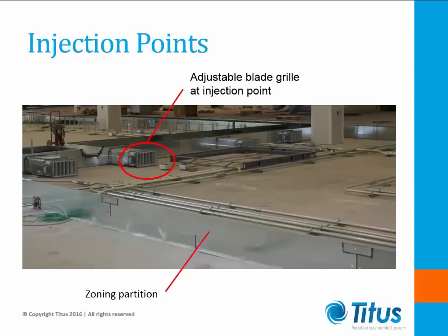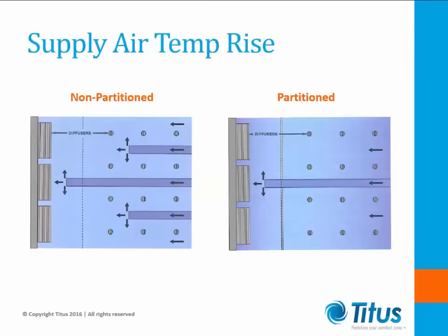In this slide, you can see both an injection point and some zone partitions. Notice that the discharge of the injection point has been fitted with a grill. You can also see how the zone partitions have been notched and sealed to go over conduit, plumbing, and other obstructions found beneath the floor. Sometimes partitioning is necessary to limit supply air temperature rise. As cool air from the air handler moves across the UFAD plenum, it is in contact with the floor panels above and the concrete slab below. In a multi-story building, the slab is also in contact with warm return air from the floor below, which tends to heat the slab and warm the supply air going to the floor above. This is why injection points need to be no further than 30 feet from the furthest diffuser.